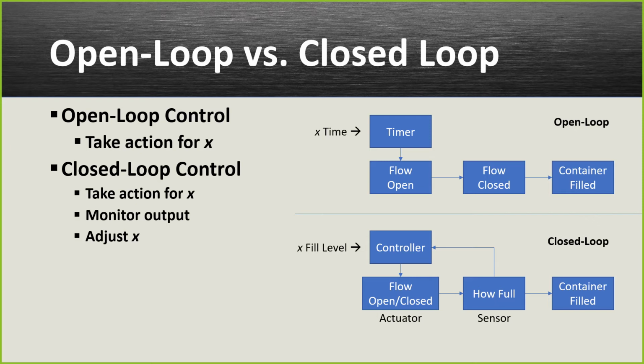We may cut it off early, we may run it longer, or not specify a time at all. We may simply say, open the flow until I tell you to close it. The controller communicates with a sensor and an actuator. The sensor evaluates how full the container is, and once it reaches the level we consider full—12 ounces, 20 ounces, 200 ounces, whatever—it sends a signal back to the controller. The controller, upon reaching that full condition, sends the actuator a command to close the flow, and now the container is filled.